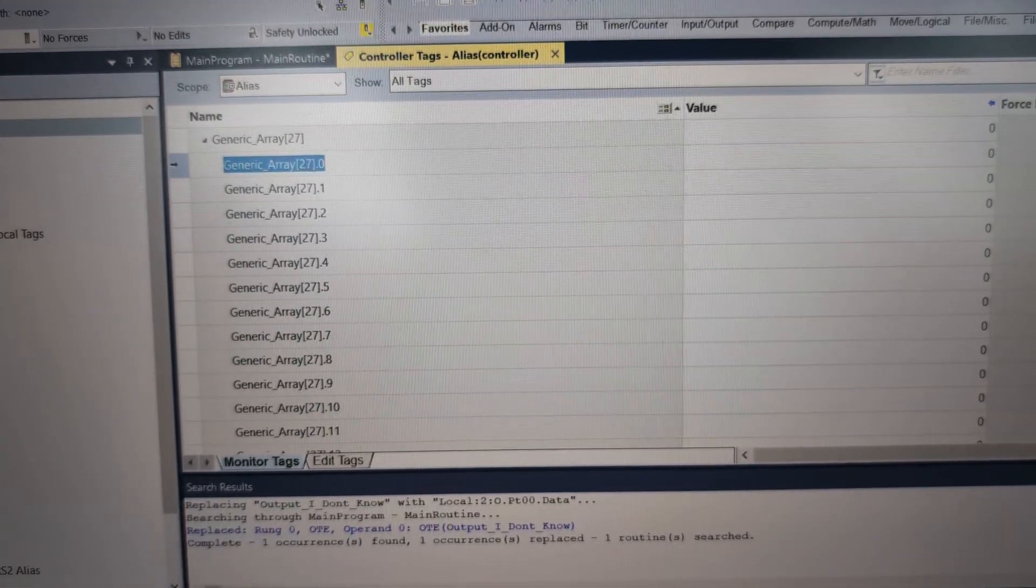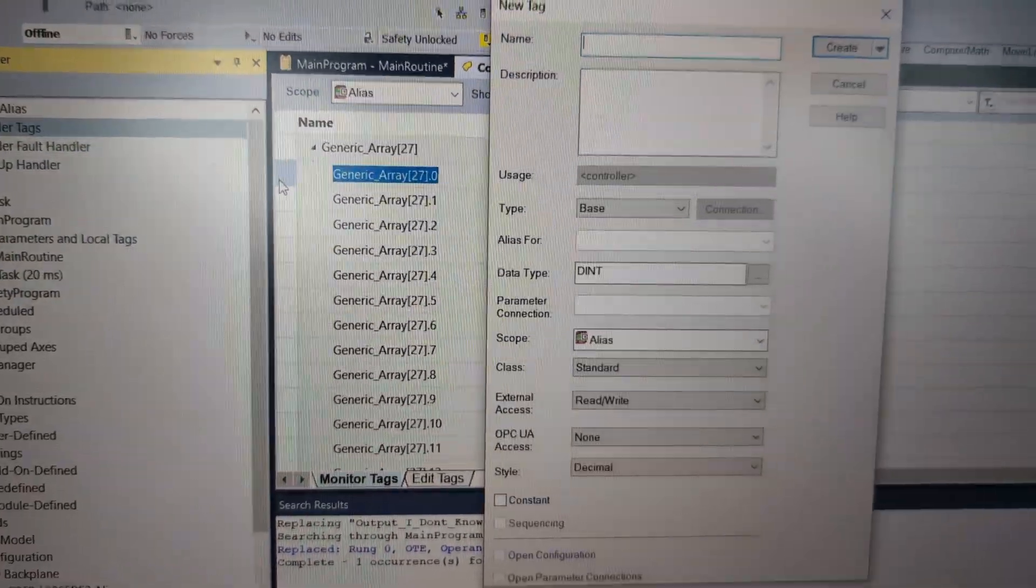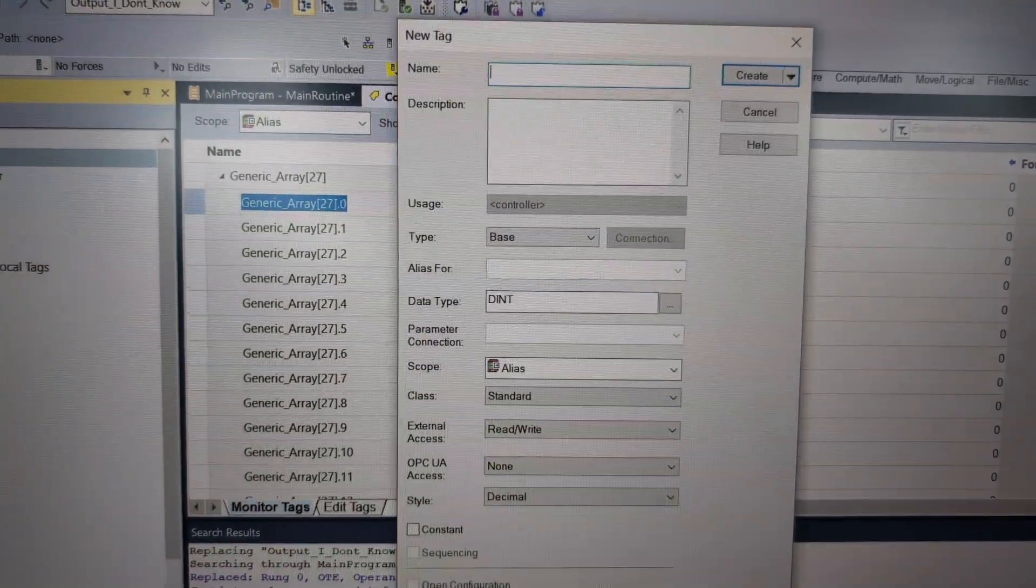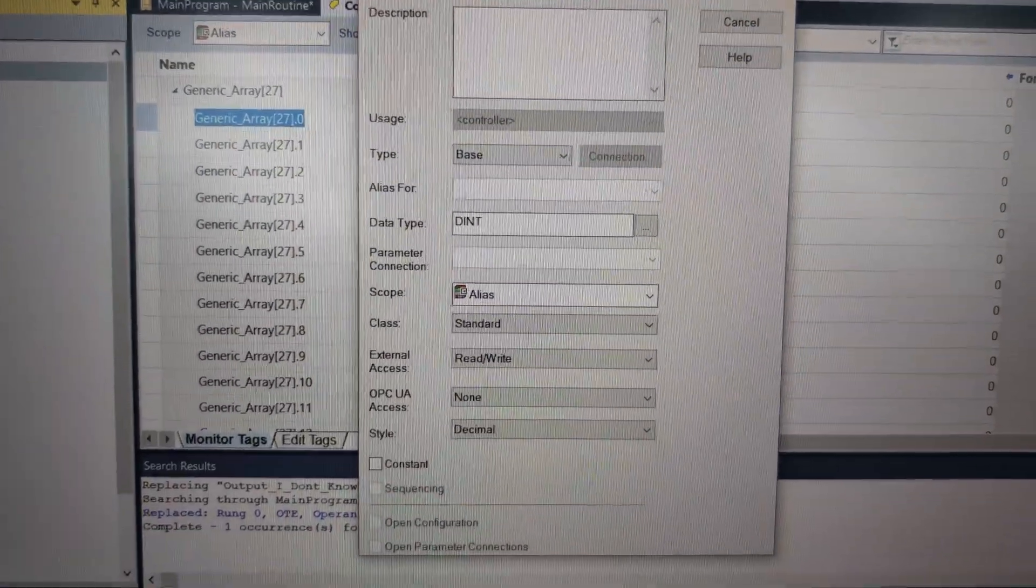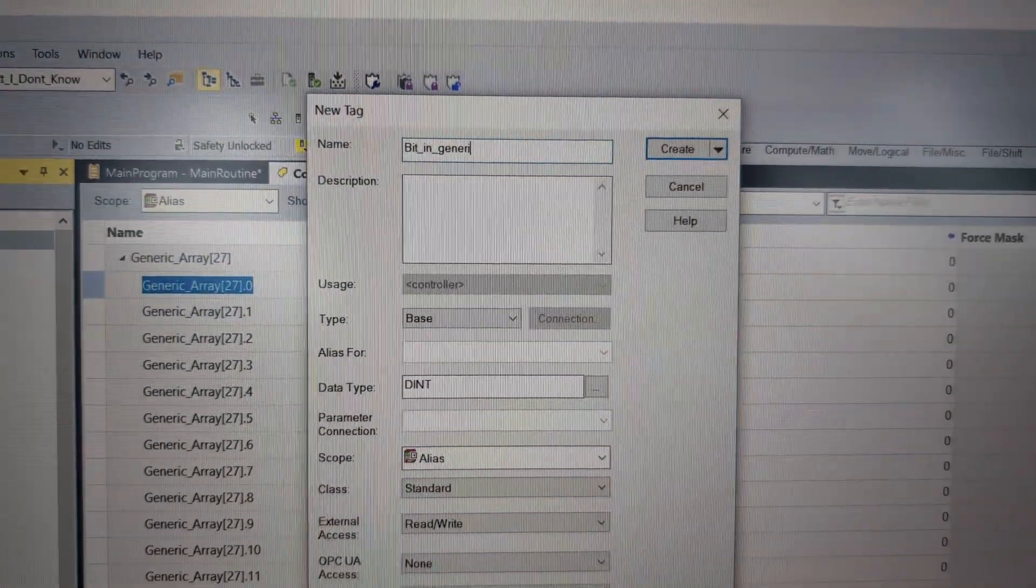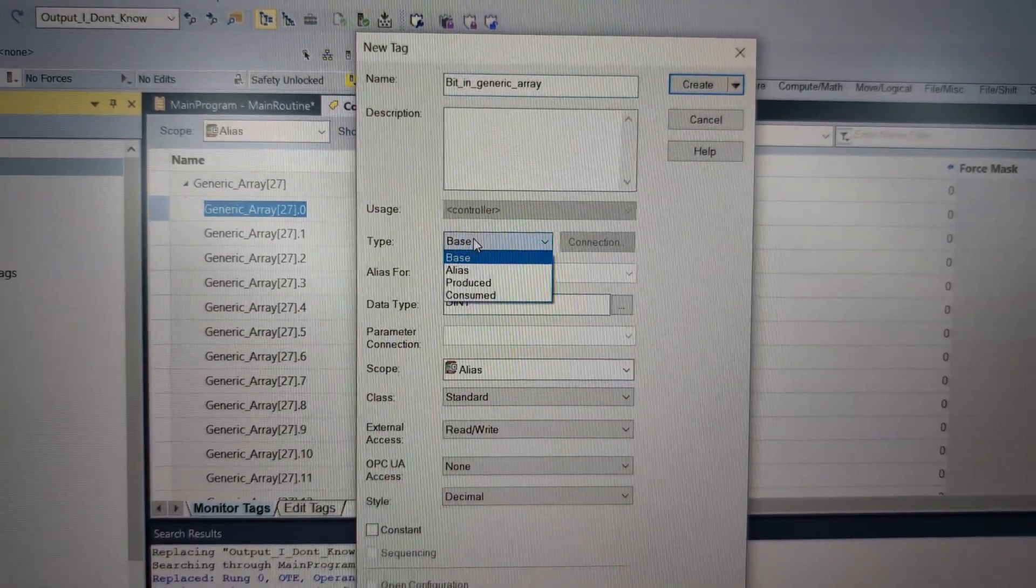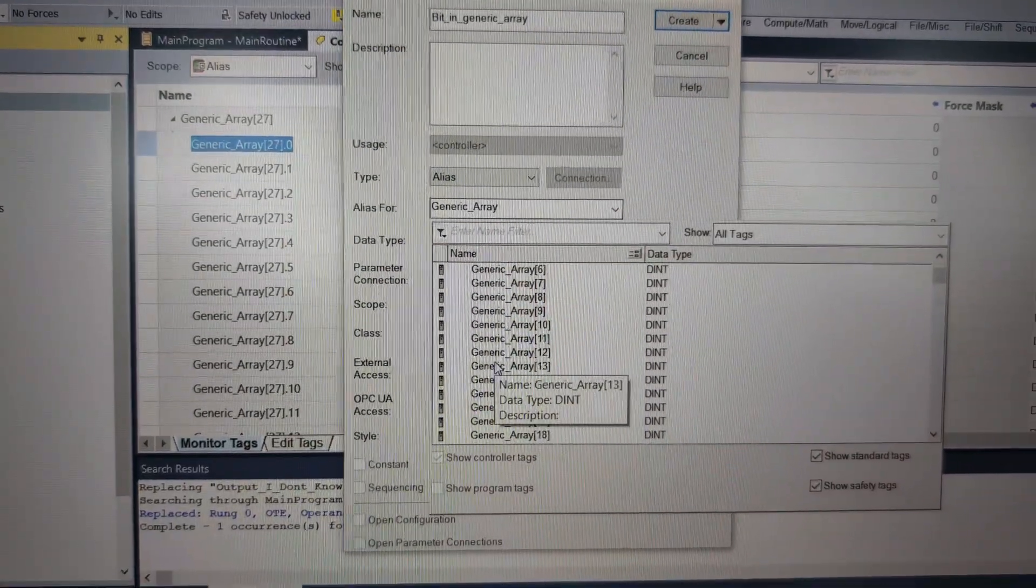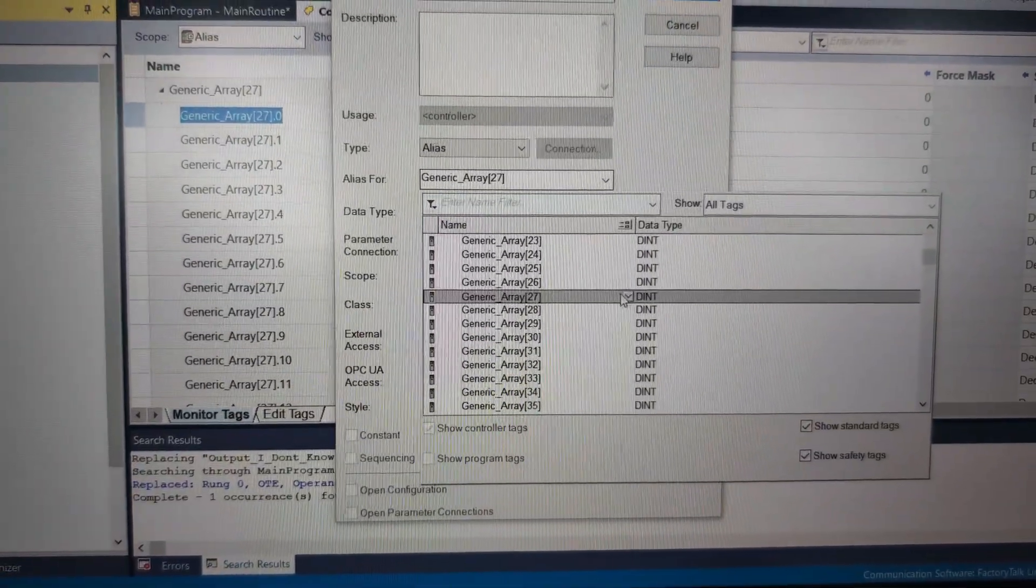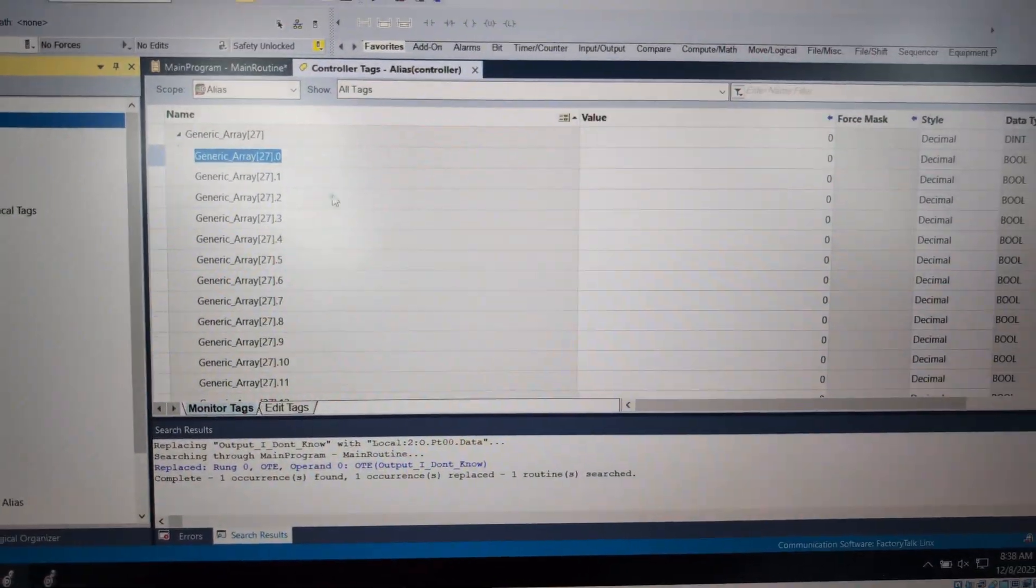So now, we have 256 generic points and we're trying to figure out what some of these items are. And I'm just going to say 27 is an I/O block that has some points on it. So 27.0, maybe that is our home switch. So what I can do is I can right click new tag over here. And instead of having to go and find this, then I could type, we're going to call this bit_in_generic_array. And I can go here and instead of having a base tag, I can drop down and get an alias and then direct underneath it. I can make it an alias for, I can open up that generic array. We can go down to 27. And then we can hit our arrow and we can get zero, create.